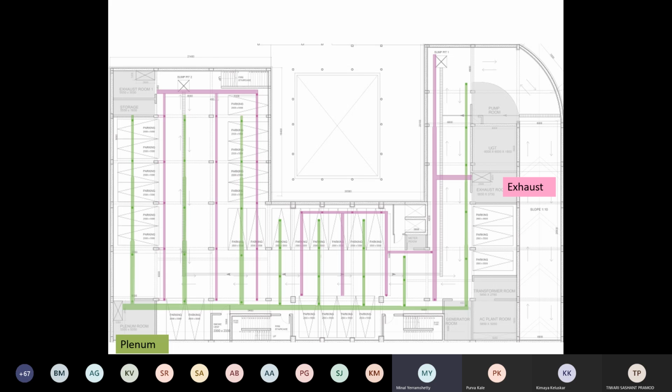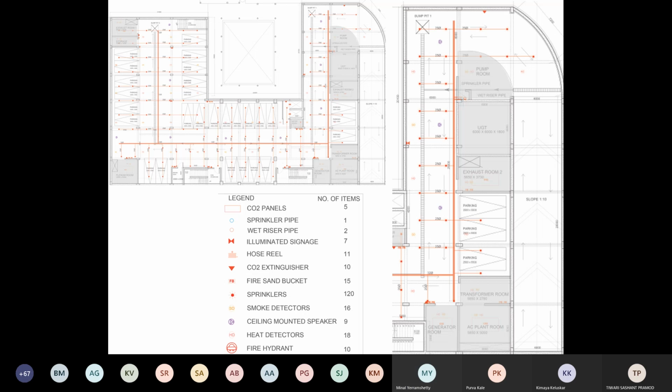Coming to the next slide, Kimaya, you will see how she has planned it. So you again see the thickness. Now do you see this, this has a telescopic way of taking the major ducts. What she has done is she has taken the main duct arising from the plenum, and then as it goes further, the secondary ducts as well as the primary ducts will go on reducing. Why will I want to have the same volume of air everywhere? Are you understanding my point, or should I elaborate on this?